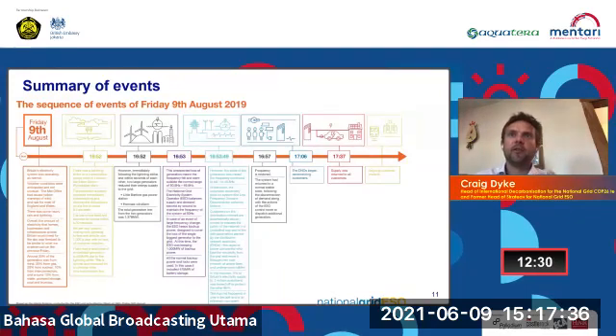What that meant for us was that we saw the frequency fall to 49.1 hertz. So back to Duncan's point, the statutory limits are 49.5 to 50.5 hertz, and we dropped down to 49.1 hertz. Frequency response kicked in, and we saw the frequency recover back up towards 50 hertz. As it started to recover, we then saw subsequent trips at Little Barford: another steam turbine tripped off, and then a gas turbine also tripped off. That meant the frequency dropped to 48.8 hertz, which triggered low frequency demand disconnection. That's demand at the distribution level that has to come off the system when the frequency drops that low, to restore the frequency back up to 50 hertz.